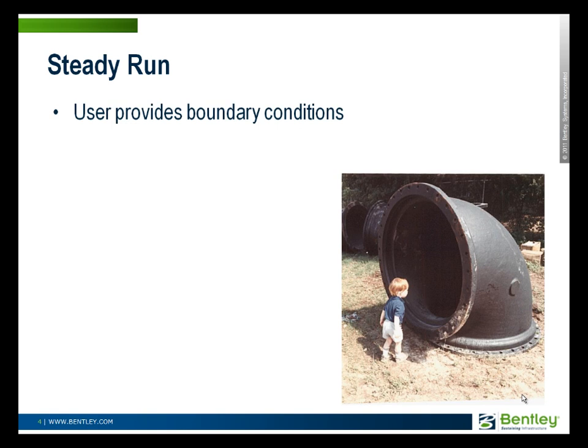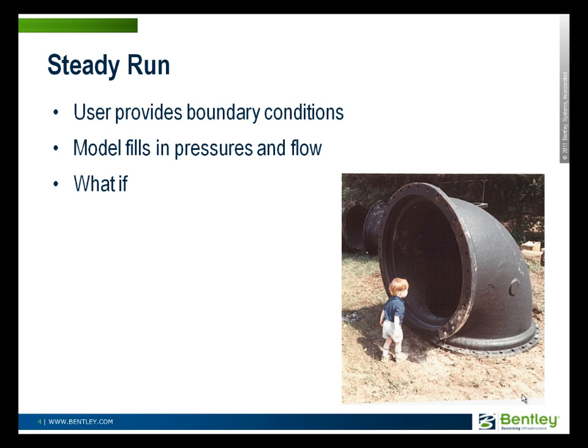The most basic run is a steady state run where you essentially provide the boundary conditions — what pumps are running, what the tank water levels are — and the model fills in all the pressures, flows, velocities, and other properties of the hydraulics of the water distribution system. So they give you essentially the ability to see what's going on inside of pipes and then ask these what-if questions.